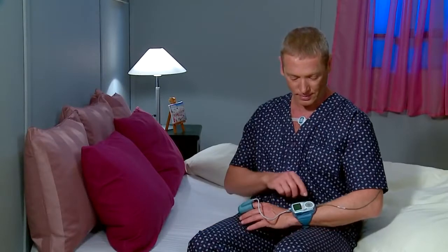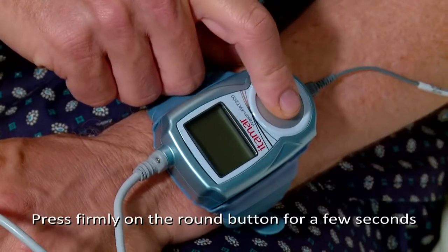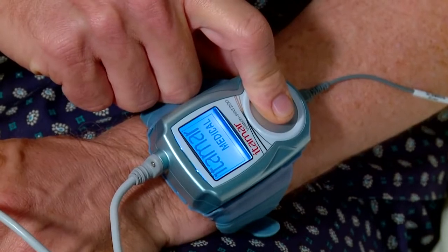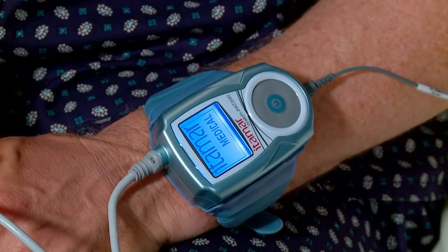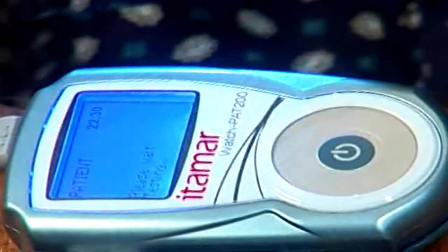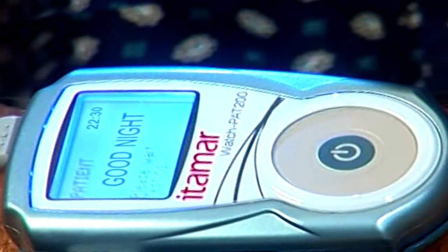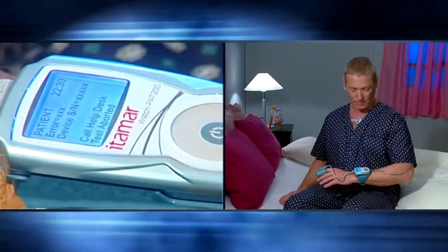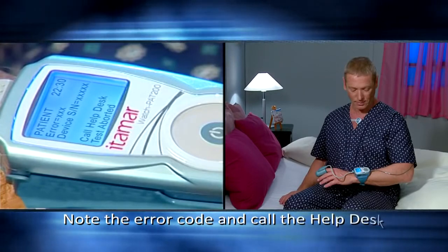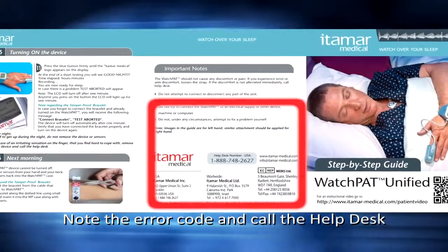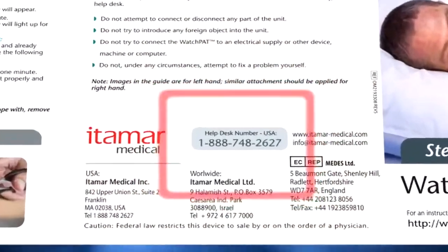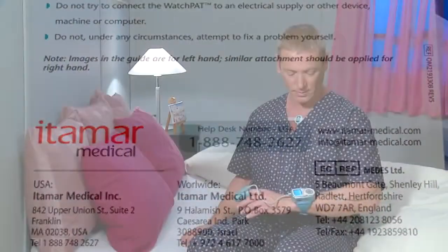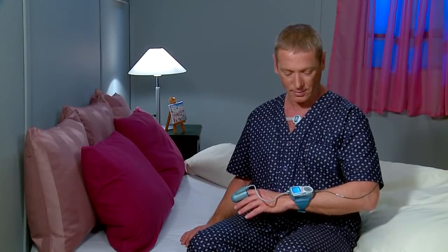Get into bed and press firmly on the round button for a few seconds. Keep pressing until Itamar Medical is displayed on the LCD screen. After about 30 seconds, a good night in the middle of the screen indicates that the study has started. If there is a problem, you will see Test Aborted. In that case, note the error code and call the help desk. WatchPAT is now working properly, and it's time to go to sleep.